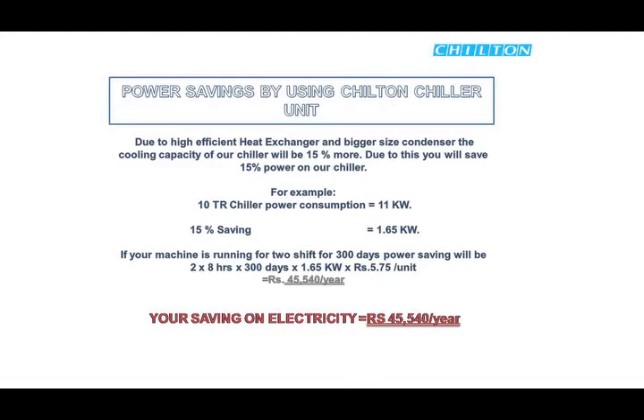If your machine is running for 2 shifts for 300 days, power savings will be 2 into 8 hours into 300 days into 1.65 kilowatts into rupees 5.75 per unit, which is equal to rupees 45,540 per year. Your saving on electricity is equal to rupees 45,540 per year.